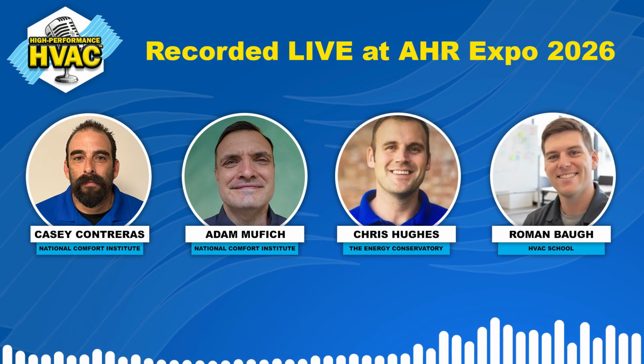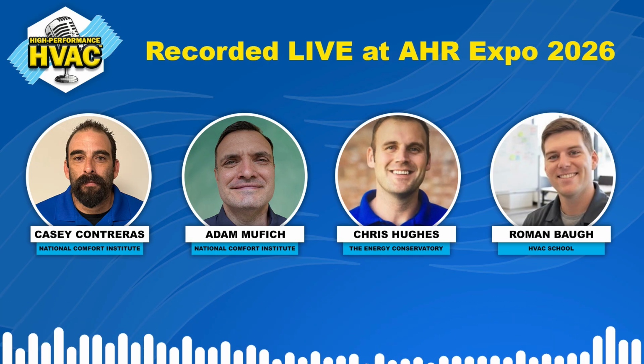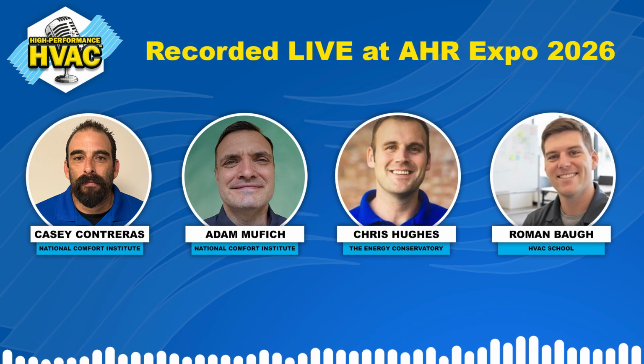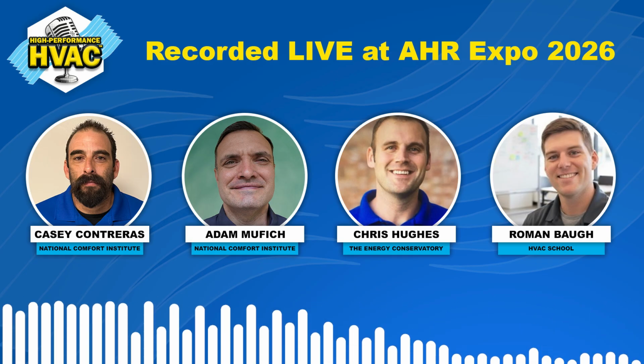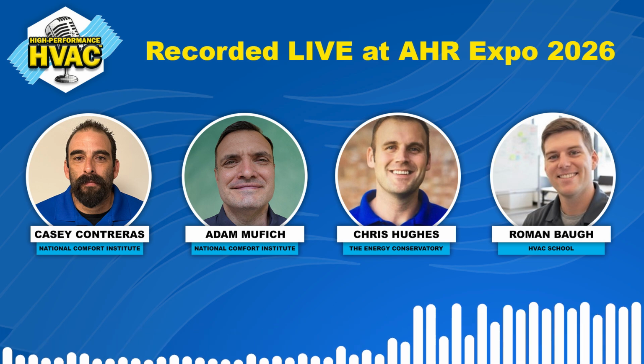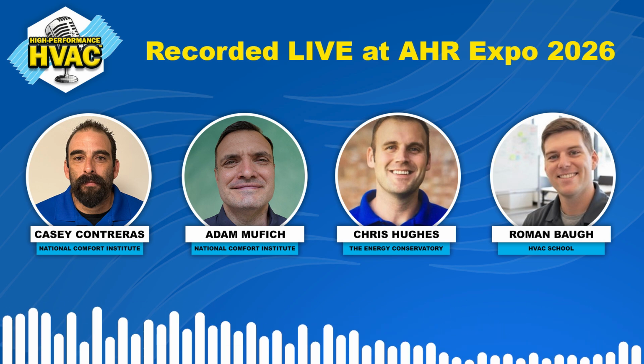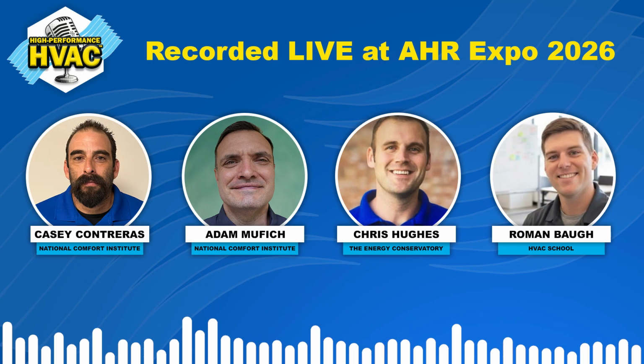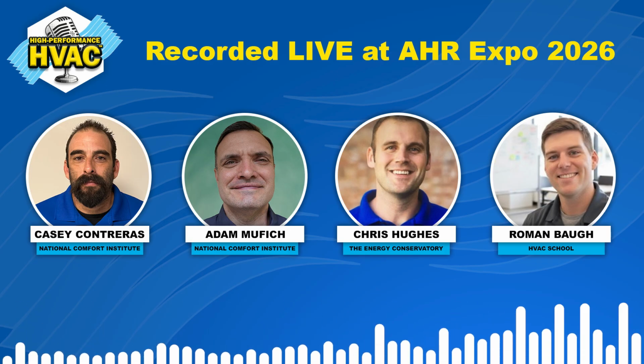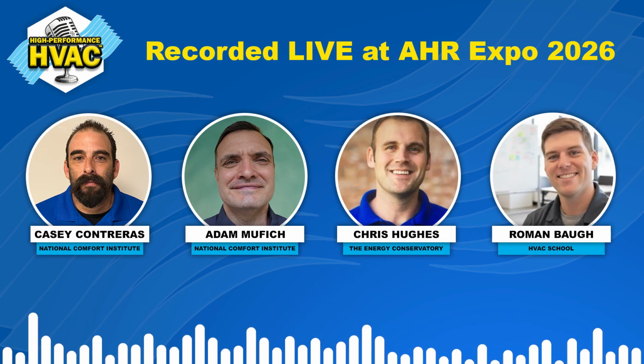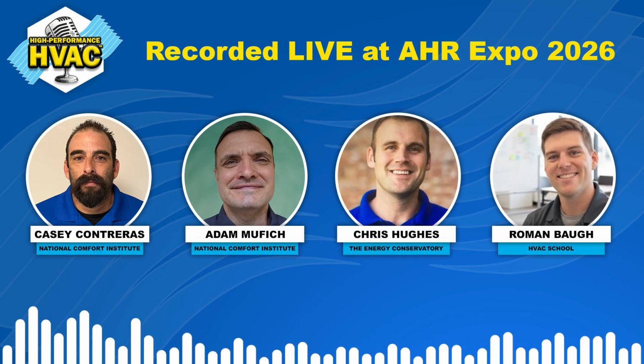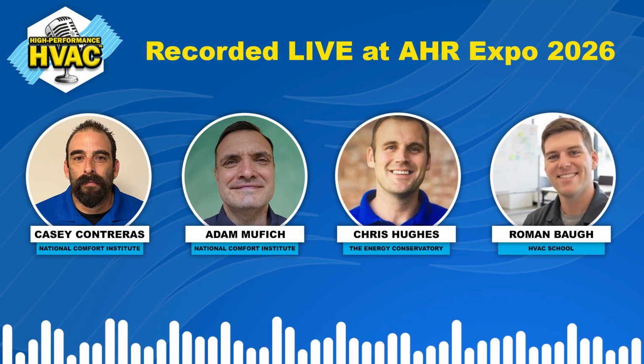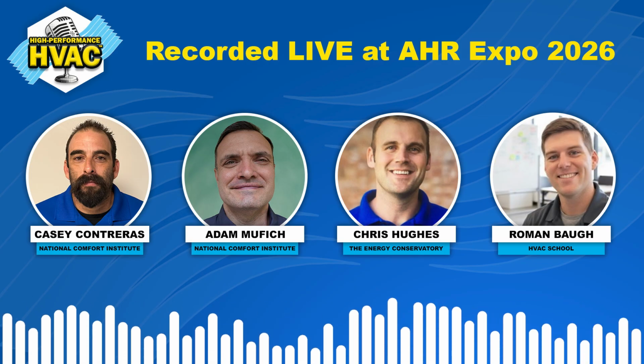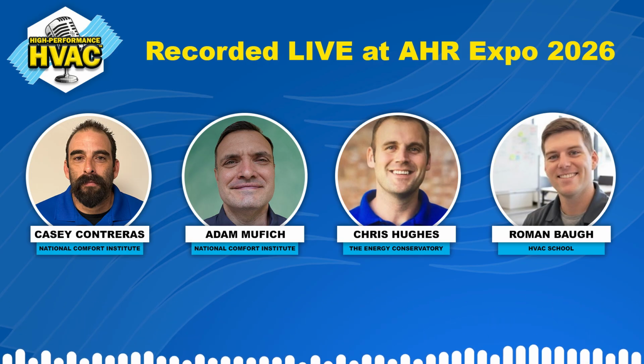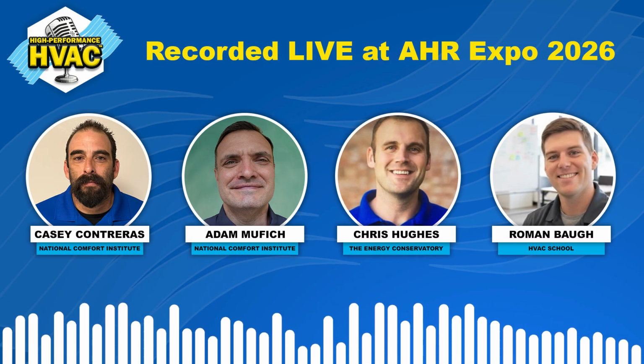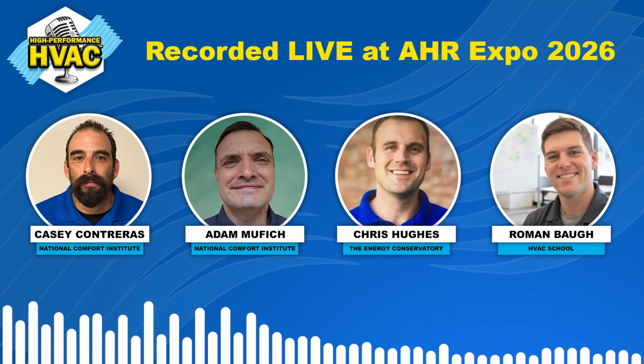Interesting. It's like an intelligent defrost pan heater. So how is the base pan heater controlled? So usually, if it's resistive, it's just a 120 volt relay on the board that says, "Hey, I'm energizing the defrost cycle. Also energize the base pan heater," so that when the water falls off, it continues to fall out of the unit from gravity and not pool up in the base of the unit. I think what you're asking, though, is whether it's driven by outdoor ambient temperature, or a sensor on the outdoor coil, or are they doing something different to make sure they're not running defrost when they don't need to? Yeah, so not defrost, pan heater.